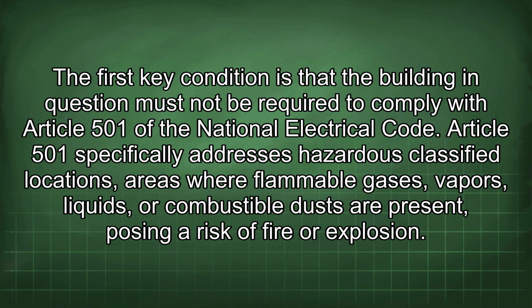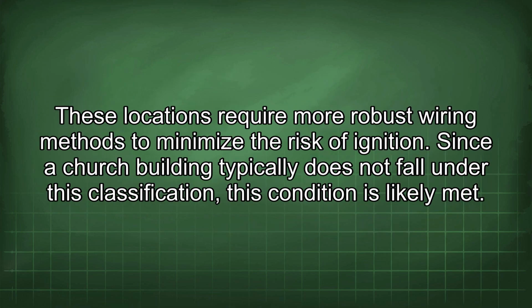The first key condition is that the building in question must not be required to comply with Article 501 of the National Electrical Code. Article 501 specifically addresses hazardous classified locations, areas where flammable gases, vapors, liquids, or combustible dusts are present, posing a risk of fire or explosion. These locations require more robust wiring methods to minimize the risk of ignition. Since a church building typically does not fall under this classification, this condition is likely met.